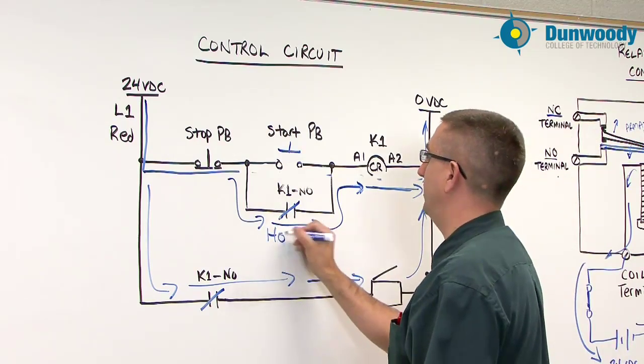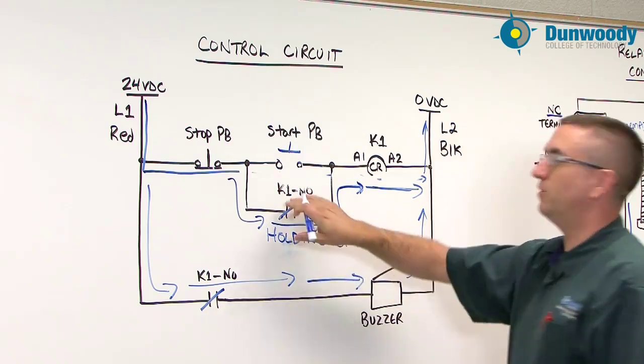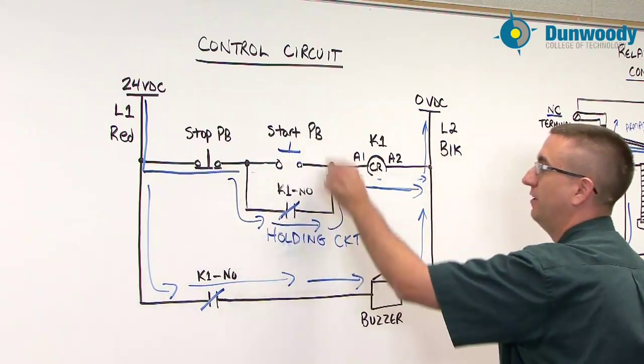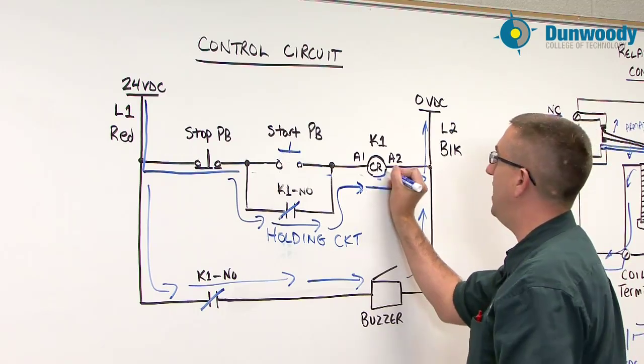And the reason why the buzzer is going to stay on is because we have a holding contact. So right here we have a holding circuit. Those contacts are not going to change state until they lose power. Well they have not lost power because no one hit the stop push button, so they haven't lost power, so they're holding this control relay on.